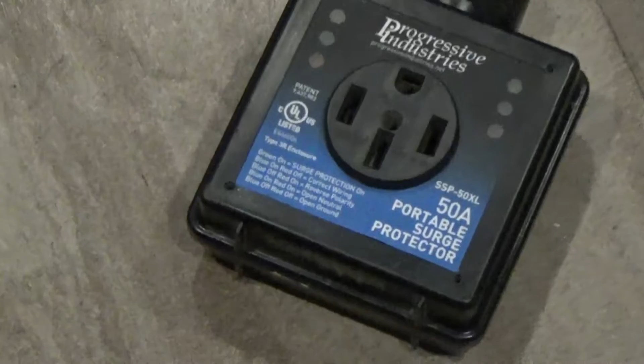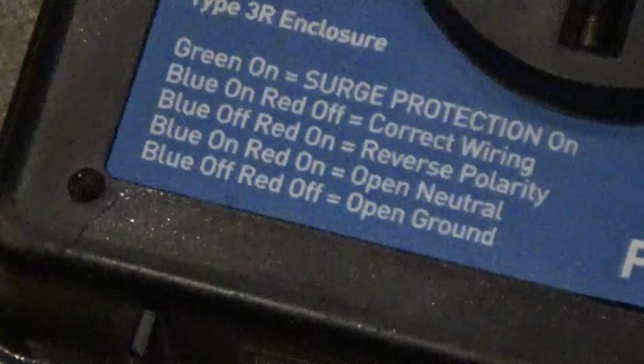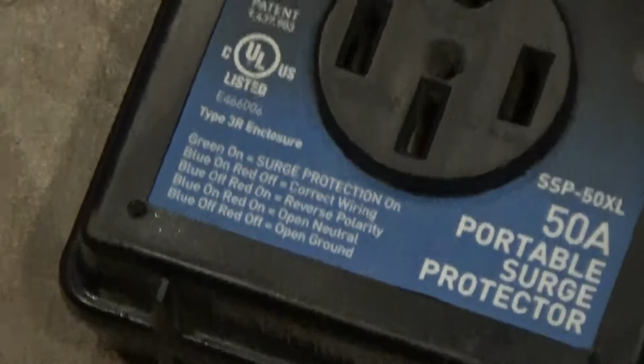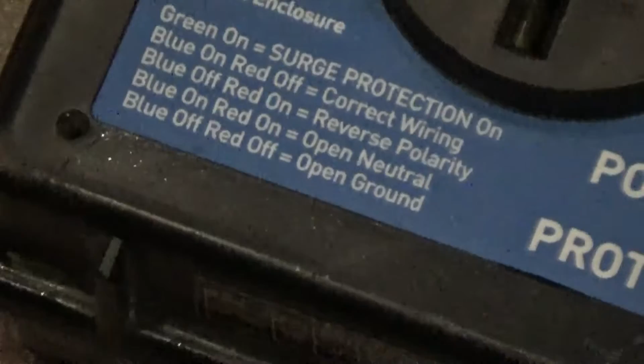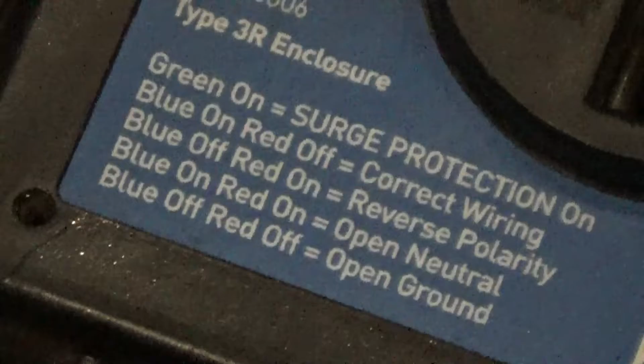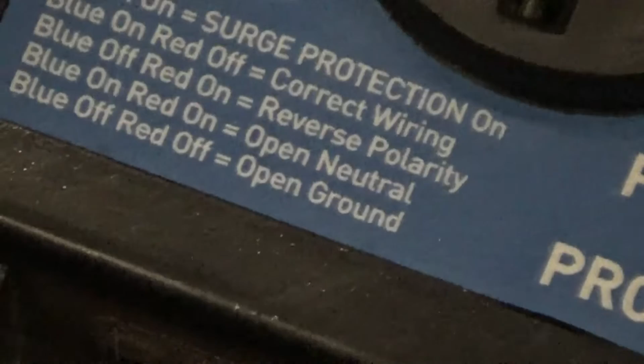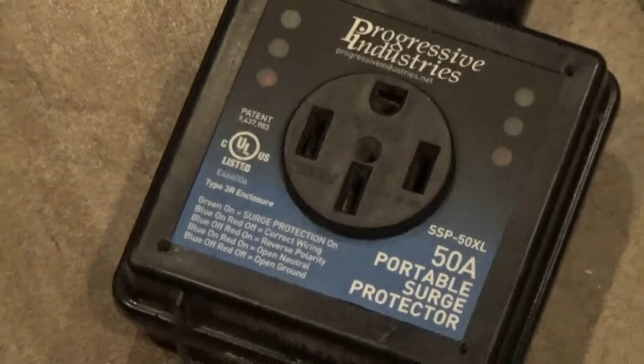Now this model here only has basically 3 features other than surge protection: these lights, green, blue, and red, for leg 1 and leg 2. If you turn it on and see green and blue lights on, then it's working perfectly. If the red light shows up, that means either reverse polarity, open neutral, or open ground is a problem. That's the only thing this small model checks for.